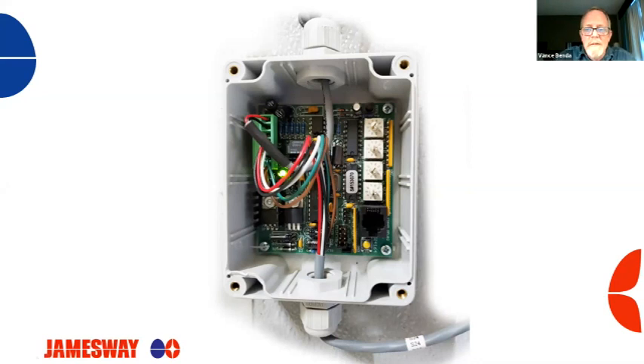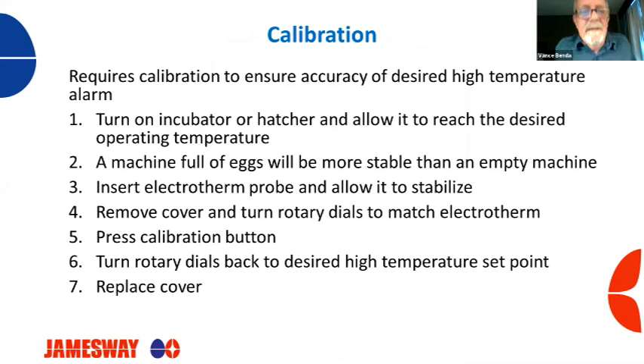All right. Now, calibrating the thermostat box is very important, because if it's not calibrated correctly, it's not going to go off when you expect it to. A lot of you are going to be familiar with some of these phrases from calibrating regular incubators, but you're basically going to want your incubator to be on and at operating temperature. We recommend calibration 12 to 24 hours after you set the machine, because right when you set a machine, it's heating, trying to heat eggs up.